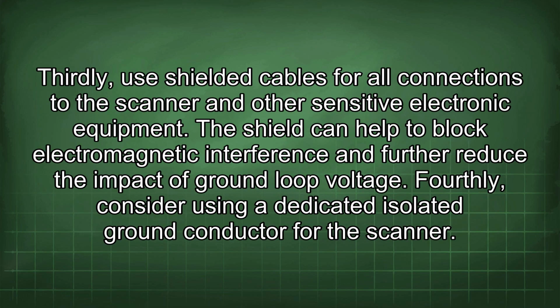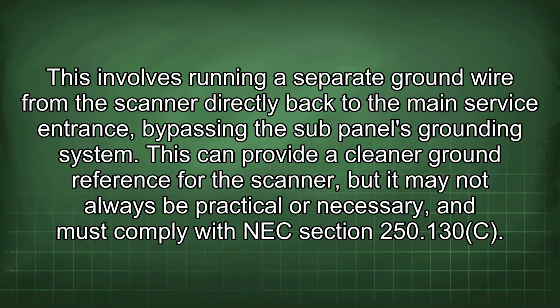Thirdly, use shielded cables for all connections to the scanner and other sensitive electronic equipment. The shield can help to block electromagnetic interference and further reduce the impact of ground loop voltage. Fourthly, consider using a dedicated isolated ground conductor for the scanner. This involves running a separate ground wire from the scanner directly back to the main service entrance, bypassing the sub-panel's grounding system.